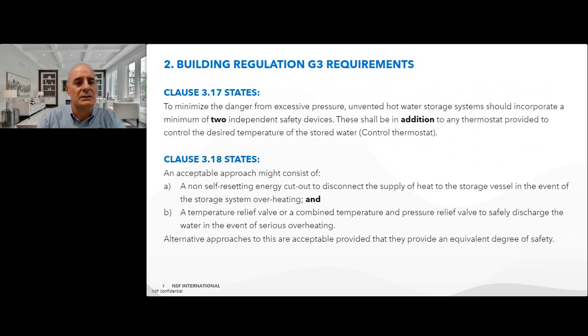Clause 3.17 states to minimize the danger from excessive pressure, unvented hot water storage systems should incorporate a minimum of 2 independent safety devices. These should be in addition to any thermostat provided to control the desired temperature of the stored water. So, two safety devices as well as the control stat.